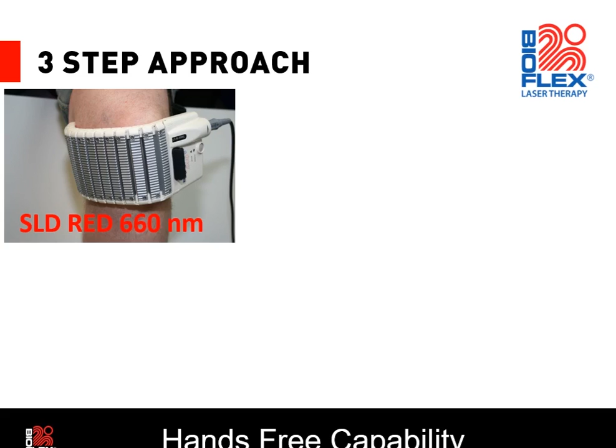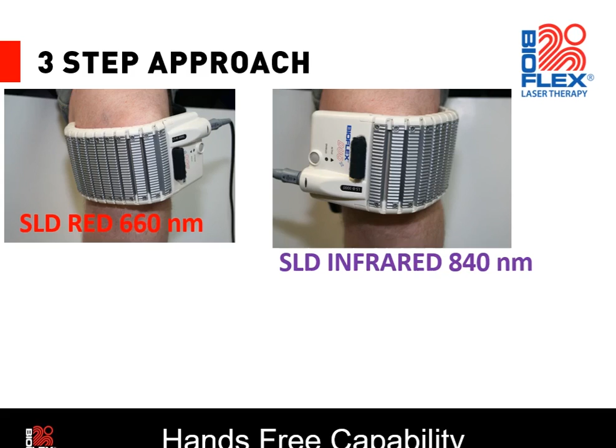Our equipment is really designed to be a three-step approach. So essentially what we're trying to do initially is to treat an area with a large surface area of an array using red wavelength, so approximately 660 nanometers with high intensity LEDs or superluminous diodes. So in the example I've shown you here, the array is strapped into position, in this case over the knee, and it's then turned on, and that tissue will be irradiated with red light anywhere from 4, 5, 6 minutes at one time. And then the next sequence of events is that light then actually turns directly into infrared light at approximately 840 nanometers in wavelength. And similarly, it is held in place for approximately the same time.